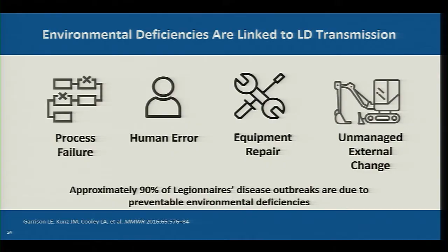For example, a process failure could be a healthcare facility that has a water management program but is missing key elements. We are starting to see this more frequently as healthcare facilities implement water management programs. On the human error side, an example might be a hotel maintenance employee who failed to perform routine checks of the hotel water heater temperatures, resulting in missing an equipment failure when the hotel water heater thermostat malfunctioned, causing the water heater to operate in the Legionella growth danger zone.